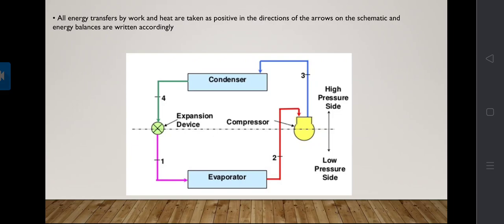In an air refrigeration system, the working medium is air, which absorbs heat from the evaporator and rejects heat in the heat exchanger, and this absorption and rejection of heat involves only sensible heat. Therefore the coefficient of performance of the system is less, and a large quantity of air is required to get the refrigerating effect. In the vapor compression system, the working medium air is replaced by a liquid, and therefore it involves sensible as well as latent heat, and the coefficient of performance of the vapor compression system is more than that of the air refrigeration system.